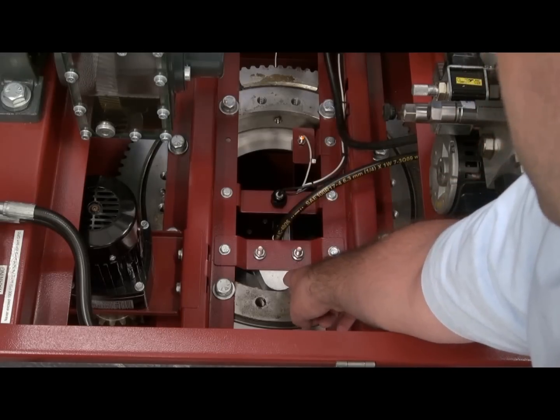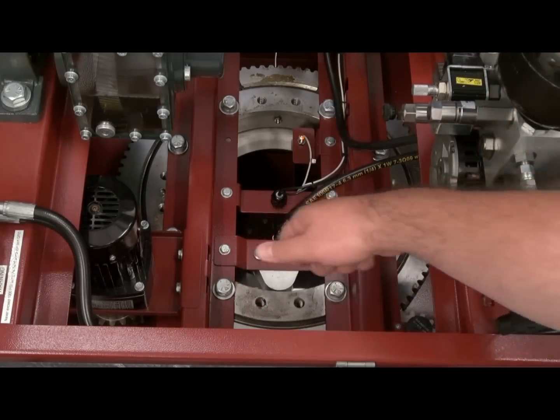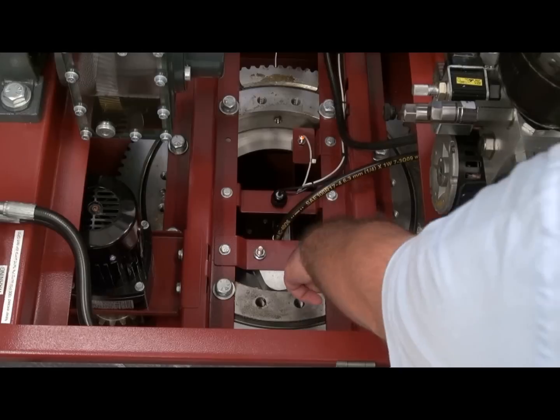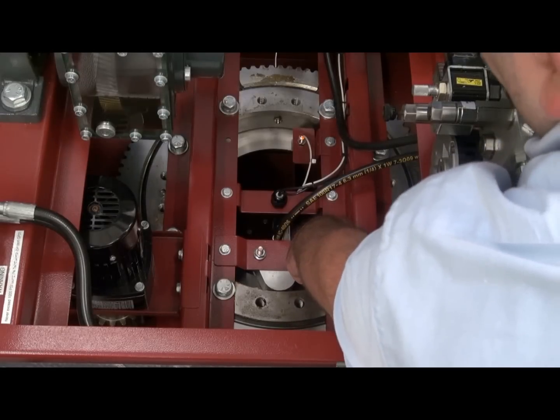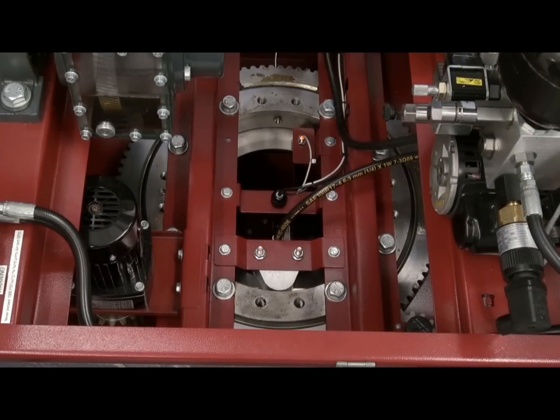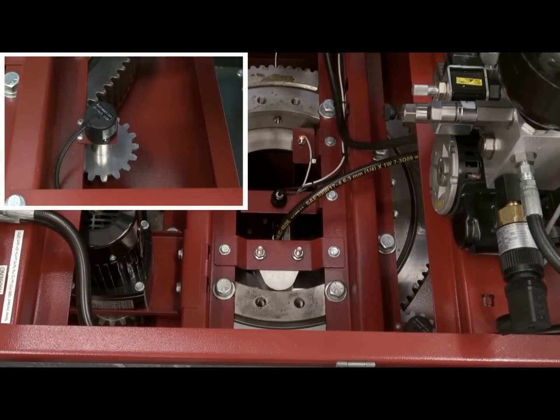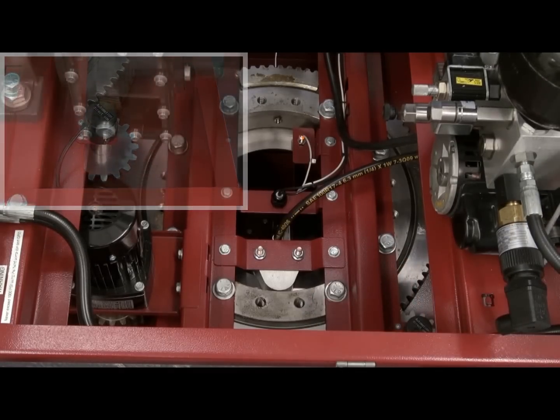You have the hydraulic hose that will go to the hydraulic brake that will stop the disc when the wind turbine is aligned with the wind. Down beneath, we also have a cable twist sensor that will detect if the nacelle has made too many turns and the power cables are twisted. We also have an optical encoder that will read the relative position of the yaw compared to the ground.